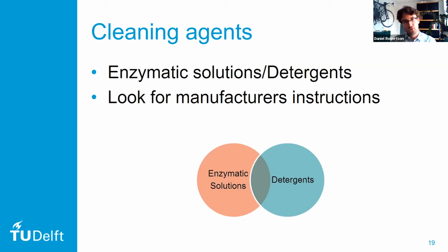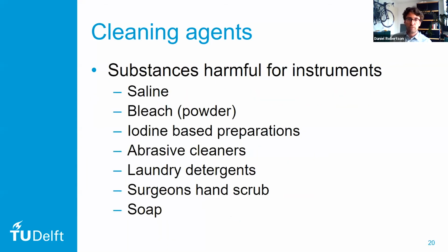And the other one is it's very important to look for the manufacturer's instructions when using some kind of cleaning solution. So the manufacturer will give instructions on what temperature it should be used at, at what dilution it should be used, and how long instruments should be soaked for the cleaning agent to become successful. Now, when we were in the rural hospitals, we saw different substances being used to clean the laparoscopic instruments and general instruments as well. And some of the substances can actually cause more damage to the instruments than they help. So one of them, for instance, is saline.